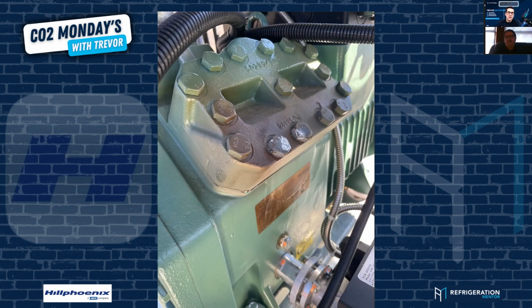Yeah, and you've got to remember when this happens, that oil inside there works at a certain temperature. So now all that oil is getting broken down. It's passing the oil separator, maybe getting logged in the system. For sure, they need to change not only the compressor, that oil would have to be changed in this system. I don't know if they did or not, but we went back and visited this site because of this. I went back a third time.